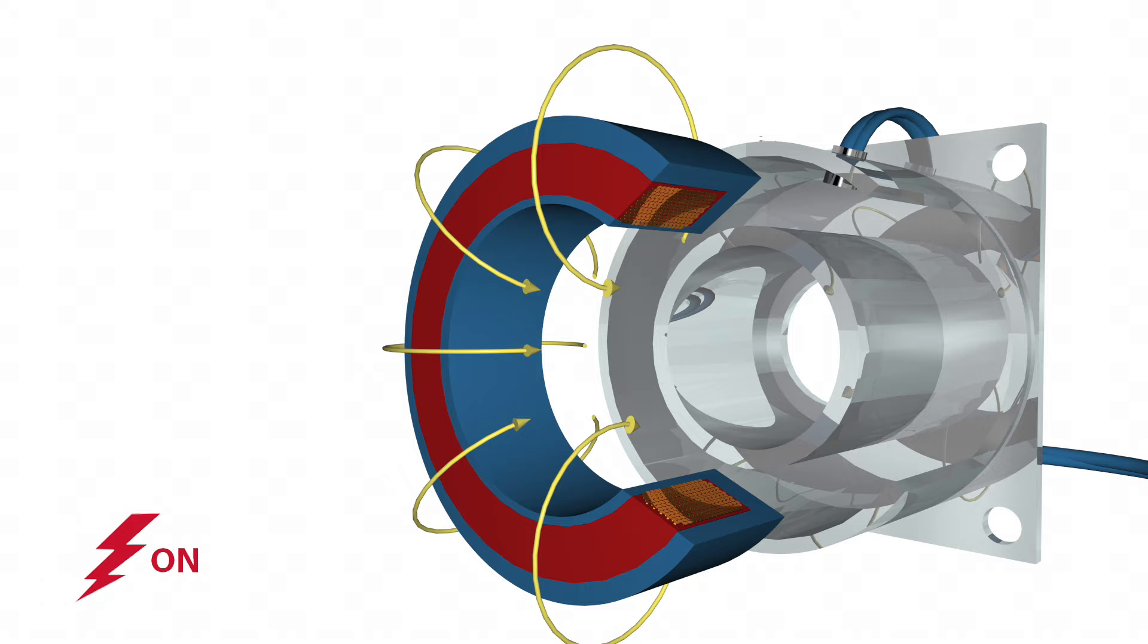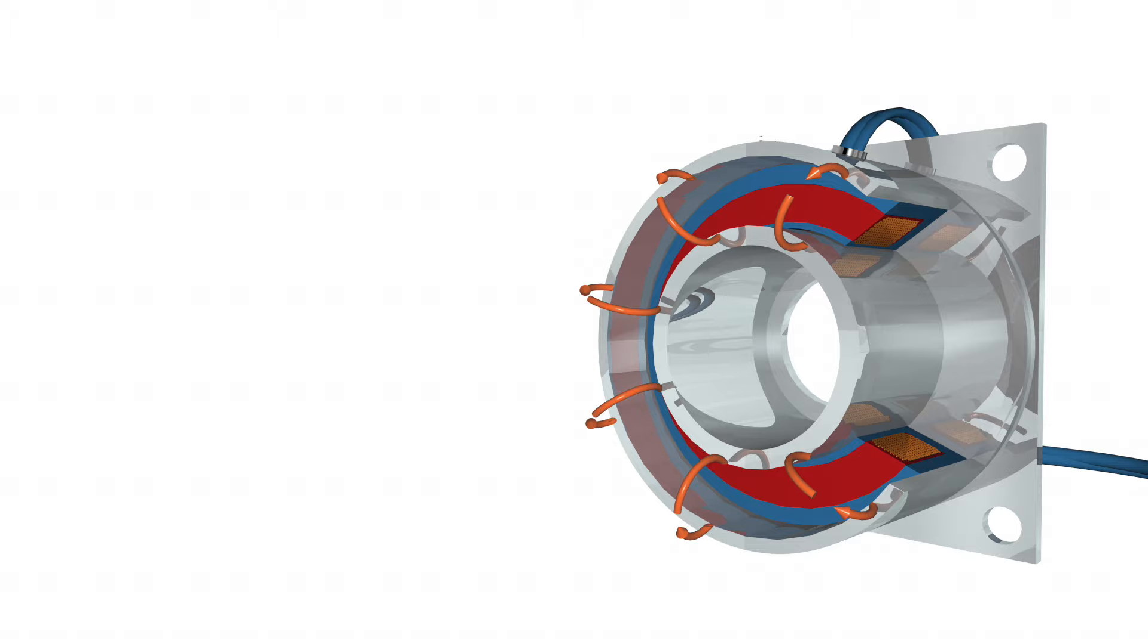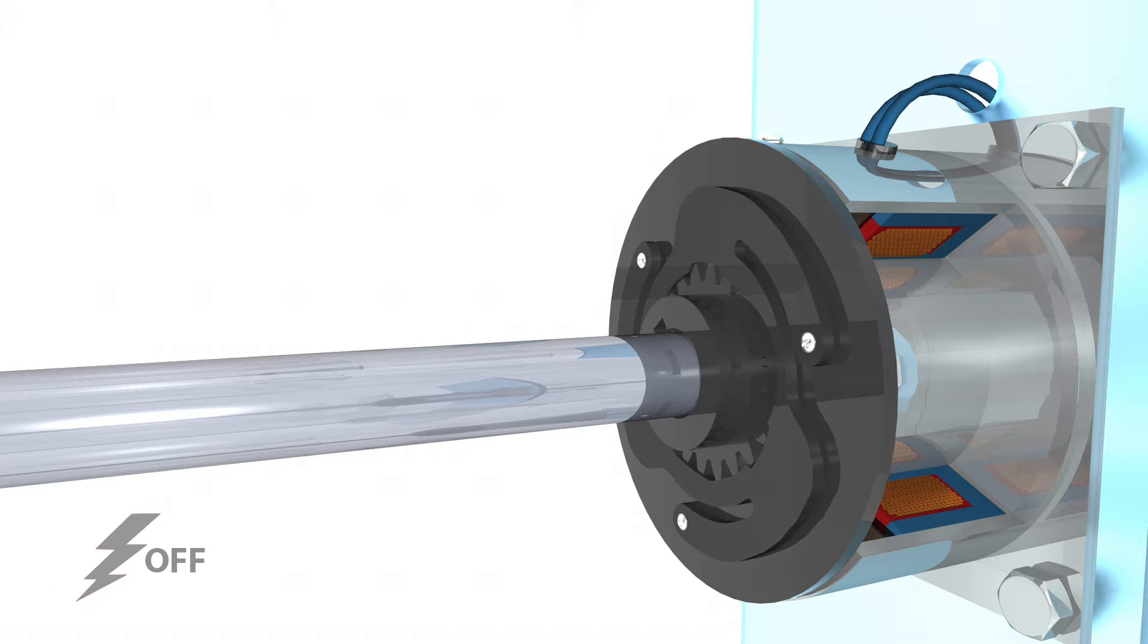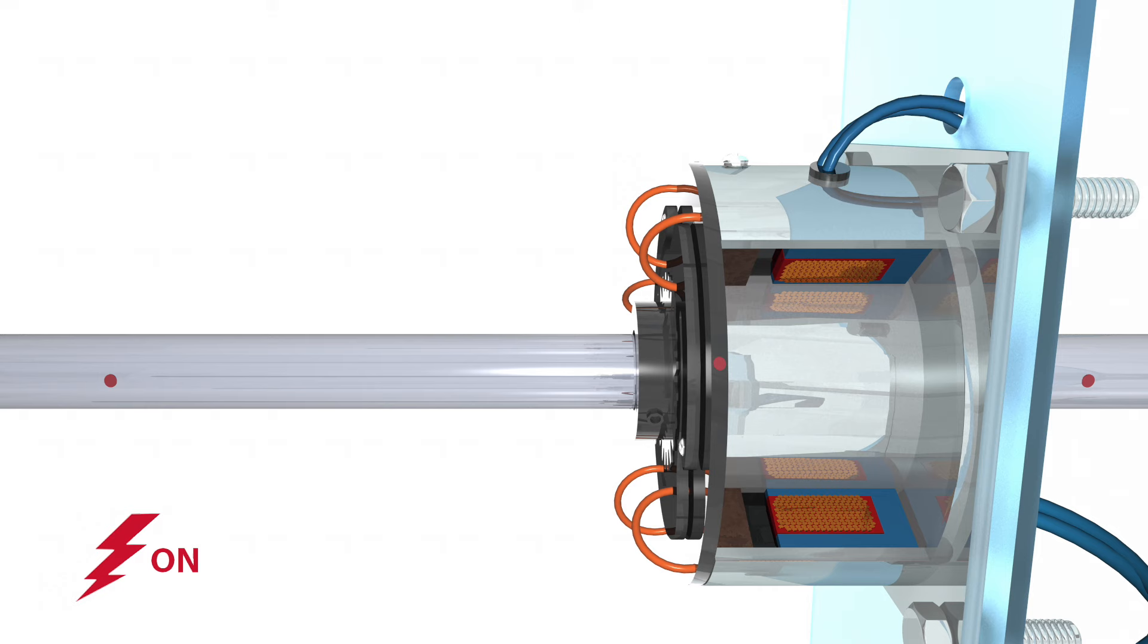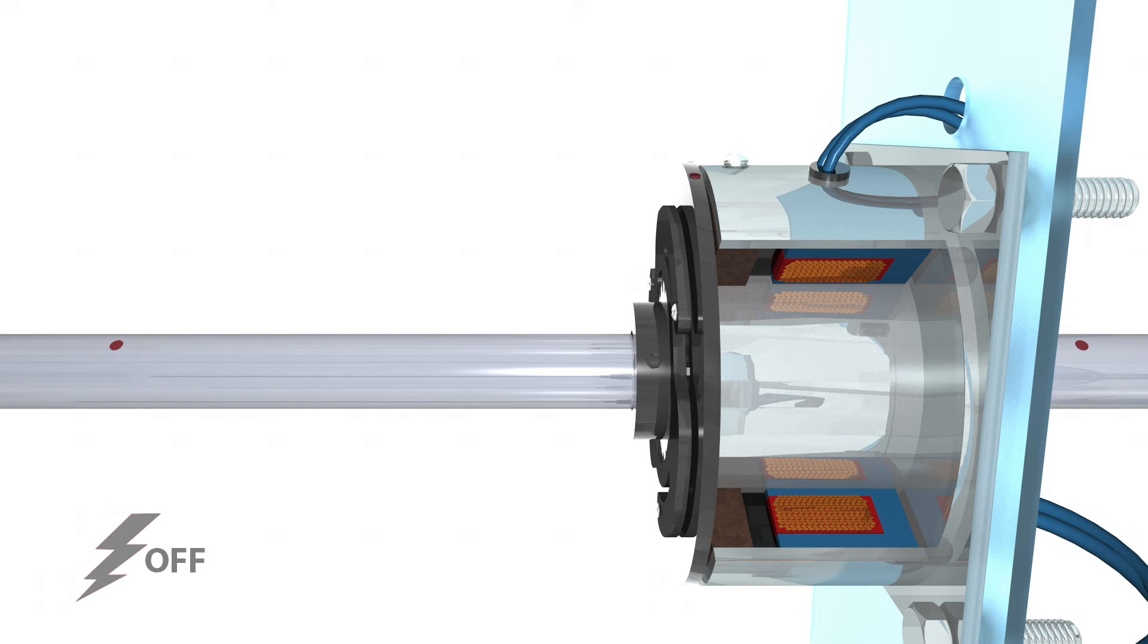Electromagnetic brakes operate via electric actuation but produce torque mechanically. When voltage or current is applied to the brake, the coil becomes an electromagnet and produces magnetic lines of flux. This flux travels through the small air gap between the field coil and the armature, magnetically pulling the armature against the hub and creating a holding force.